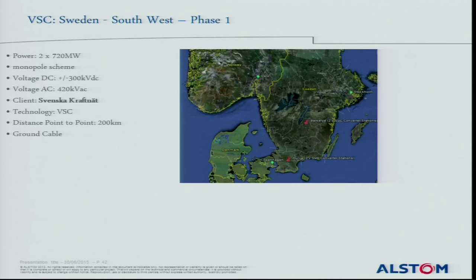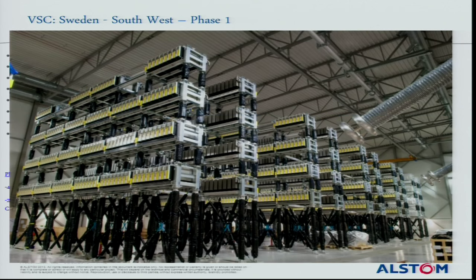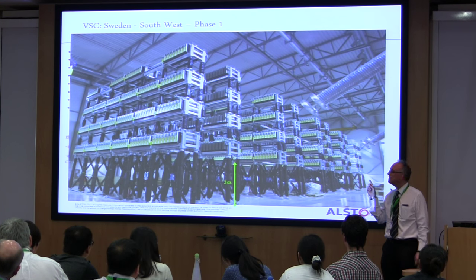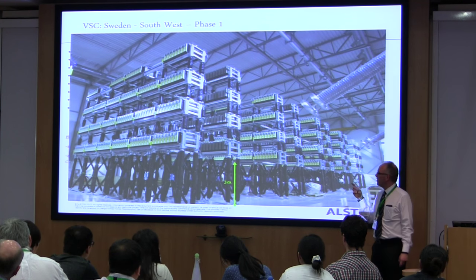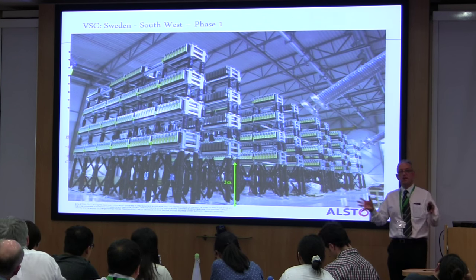As an example of a scheme under construction — 300 kV DC, 720 MW symmetrical monopole, being built in Sweden between Barkeryd and Hovekulla. That's a picture of the valve under construction. We talk a lot about the volume of power electronics and efforts to reduce it, but the power electronics represent probably about 20% of the volume of the valve hall — if that. Most of the valve hall is air, because at 300 kV you need about two and a half metres of air to stop it flashing over. So making it smaller isn't the big driver for us as it is for some other industries.